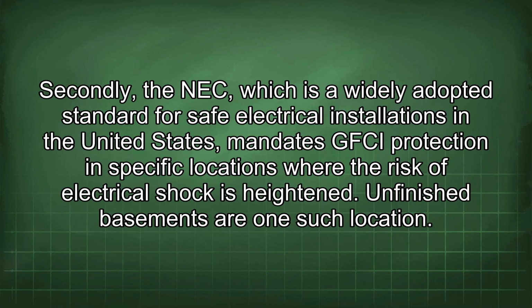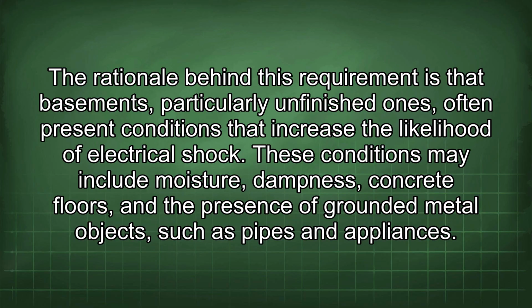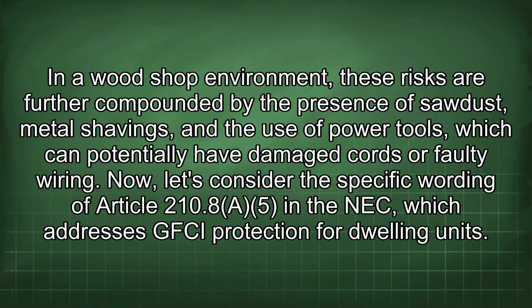Secondly, the NEC, which is a widely adopted standard for safe electrical installations in the United States, mandates GFCI protection in specific locations where the risk of electrical shock is heightened. Unfinished basements are one such location. The rationale behind this requirement is that basements, particularly unfinished ones, often present conditions that increase the likelihood of electrical shock. These conditions may include moisture, dampness, concrete floors, and the presence of grounded metal objects such as pipes and appliances. In a woodshop environment, these risks are further compounded by the presence of sawdust, metal shavings, and the use of power tools, which can potentially have damaged cords or faulty wiring.